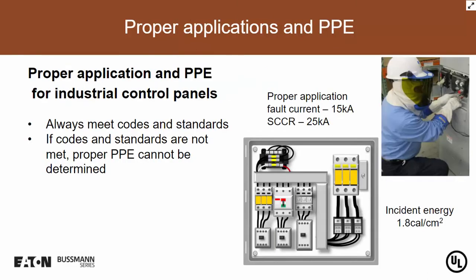So let's look at what PPE do I need to wear, okay? We basically have already determined our short circuit current rating, and in this case, we determined that our short circuit current rating for this panel is 25 kA. The available fault current is 15,000 amps, right? And we've calculated our arc flash. The incident energy level is 1.8 calories per centimeter squared, which would be a hazard category or a PPE level 1, which means that I would wear a 4-calorie shirt, 4-calorie pants, 4-calorie face shield, rubber gloves, leather protectors. And that would cover me for this panel, and everything is adequate.